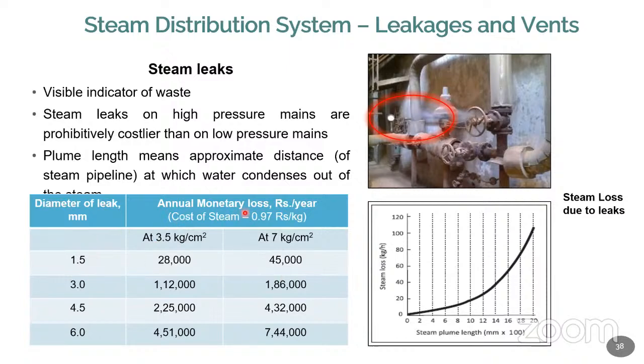The annual loss in terms of money: for example, if the cost of the steam is 1 rupee per kg, at 3.5 bar pressure or at 7 bar pressure, this is the amount of money you are wasting, because you are producing the steam by giving energy, by giving money, by giving manpower. So if you are wasting steam, automatically the cost is wasted. See the very important point.